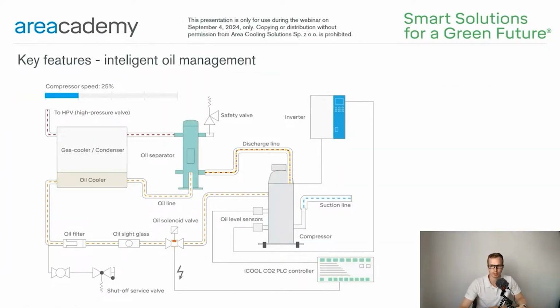The second added value when choosing iCool CO2 is the intelligent oil control system. Oil management is crucial, especially in CO2 refrigeration installations. The return of oil can be a challenge in multi-evaporator systems with capacity modulation. That is why the iCool CO2 unit features an efficient oil management system consisting of built-in software in the controller to push back the oil to the compressor, the oil separator as standard, and electronic oil level sensors, the minimum and maximum oil level on the compressor.